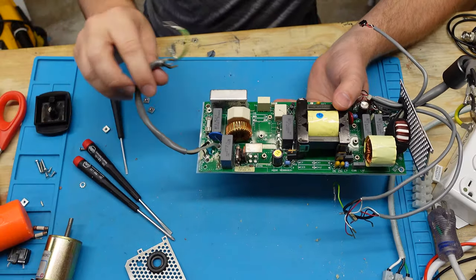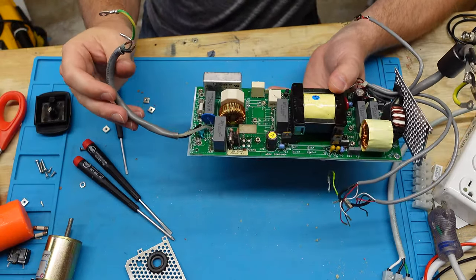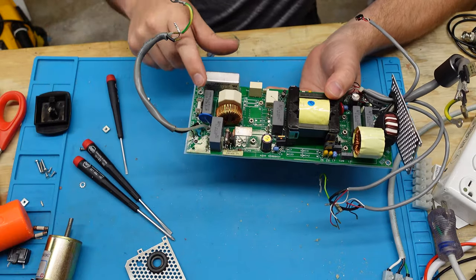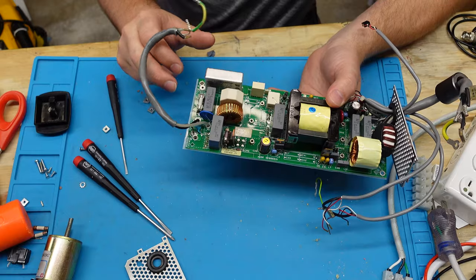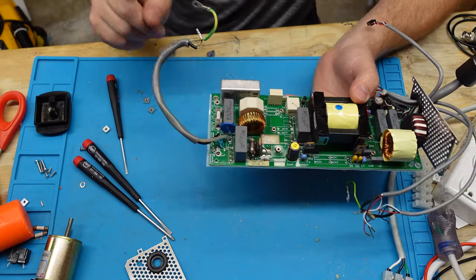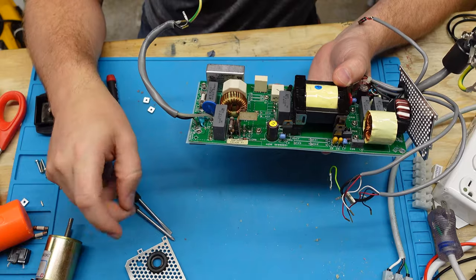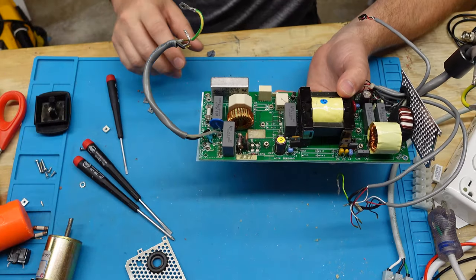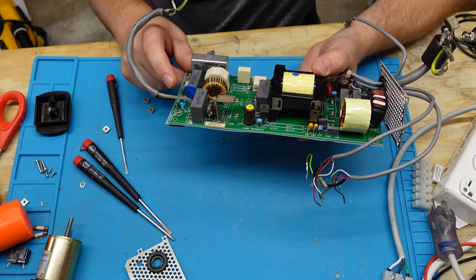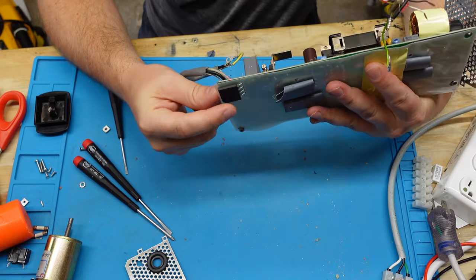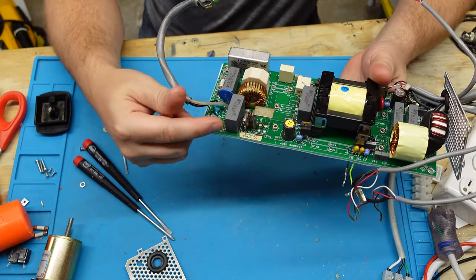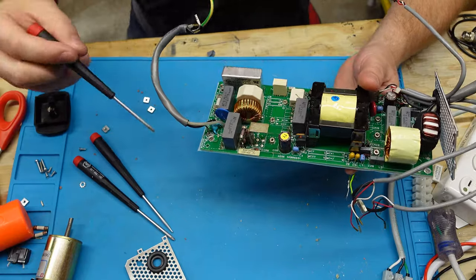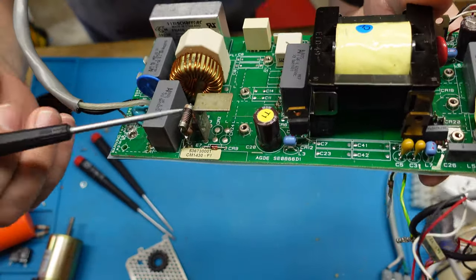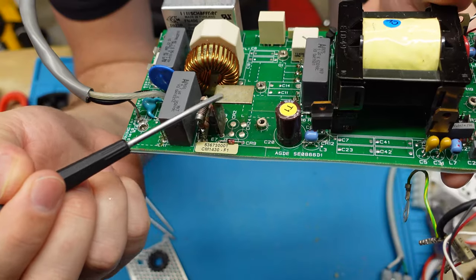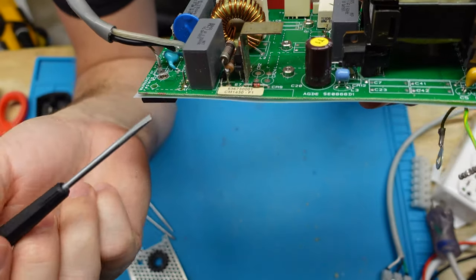So your AC power comes in right here on this side, and it comes through here. We have filtration, inductors and capacitors, and your main fuse, which there's only one fuse on this board, which, as you guys have heard me talk about, medical grade power supplies usually have two. Inrush current resistance and your bridge rectifier mounted right here on the bottom. And take a look at that.